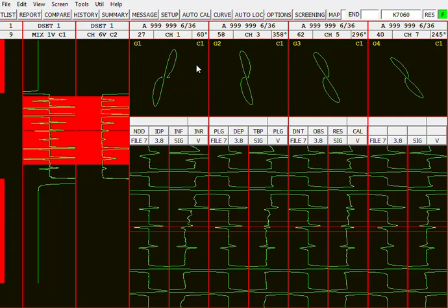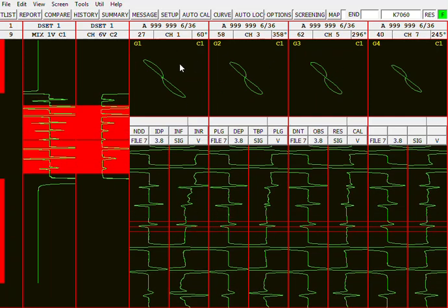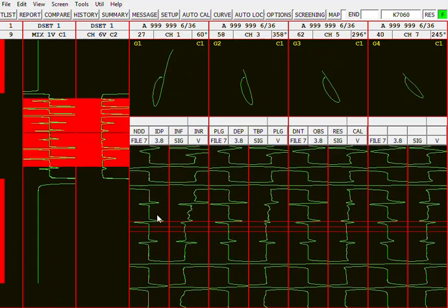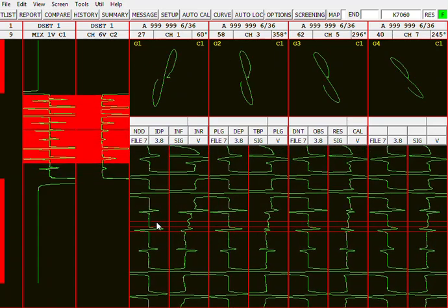Notice the phase difference. So remember, the 100% hole is 40 degrees on all of these channels because that's where I set it. But when you leave that signal set at that rotation and you go visit another flaw in the cal standard, now you'll see the phase lag play into our phase analysis. The highest frequency channel has more phase lag because you don't have a flaw right at the inside surface of the tube.